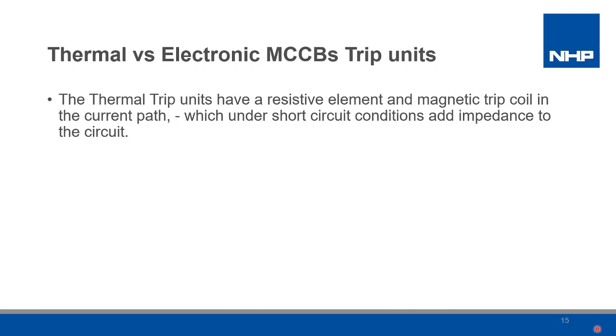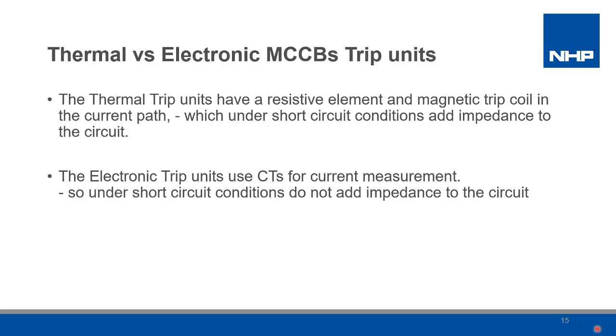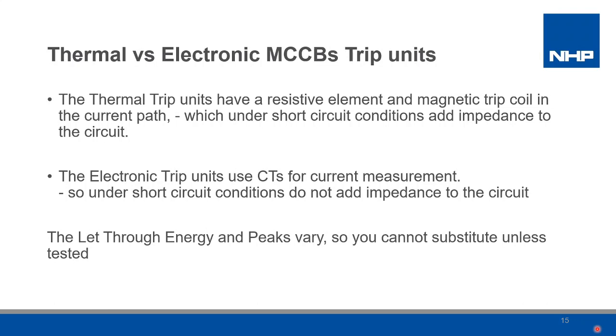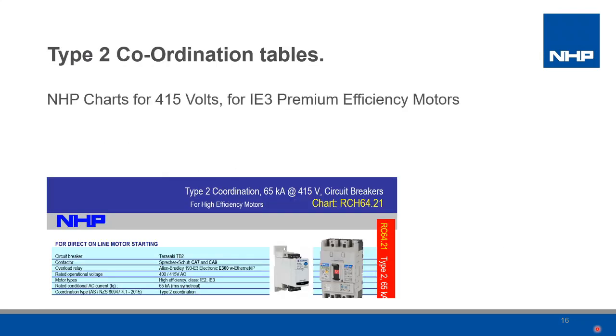The MCCBs with thermal trip units have resistive elements, which add to the total circuit impedance, which helps reduce the peak let-through energy during opening, whereas an electronic unit does not. As the let-through energy and tripping times can vary, both trip unit variants have to be tested. We have tested the Terasaki MCCBs with Rockwell Brand's Allen Bradley combinations.